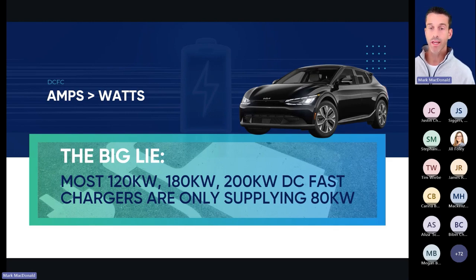Most 120, 180, and 200 kilowatt chargers deployed over the last 5+ years, if you plug in with the typical vehicle in North America, you're only able to pull about 80 kilowatts. So if you're a contractor or specifier involved in selecting this equipment, the amperage of the cable is more important to charging experience than the total watts that fast charger can supply.